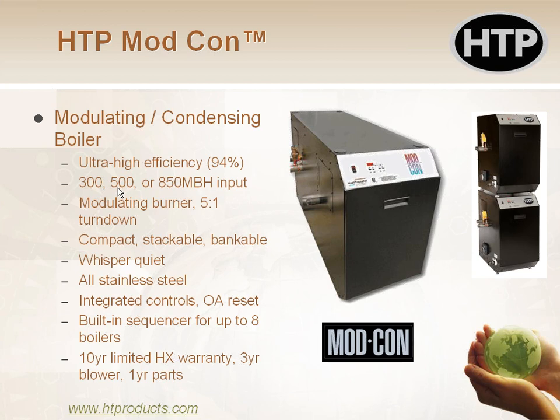They have a built-in sequencer for up to 8 boilers. So one becomes the master, and the other 3, 4, 5, 7 of them or whatever become the subordinates, and they're listening to instructions from the master. And you can also stack them too. They have the ability to take 2 boilers of the same size and stack them on top of each other with no additional framing or support required. They go right on top of one another.